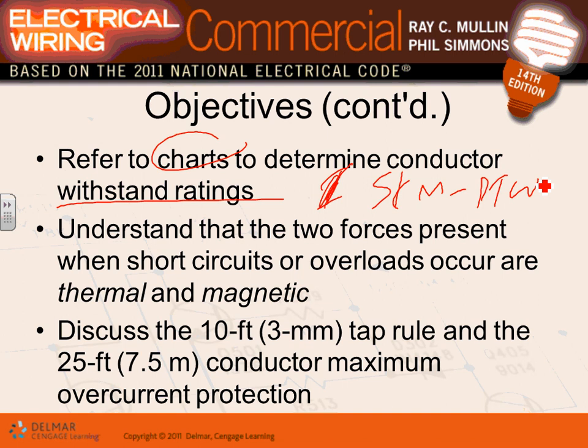Every time you have a short circuit condition, you have two forces acting on your equipment, the evils. The two evil things, two forces, present when you have a short circuit or an overload protection. One of them is called thermal, that's heat. And the second one, gentlemen, is called magnetic. When you have a short circuit inside that panel there, this panel is being cooked. I call it shake and bake, right?